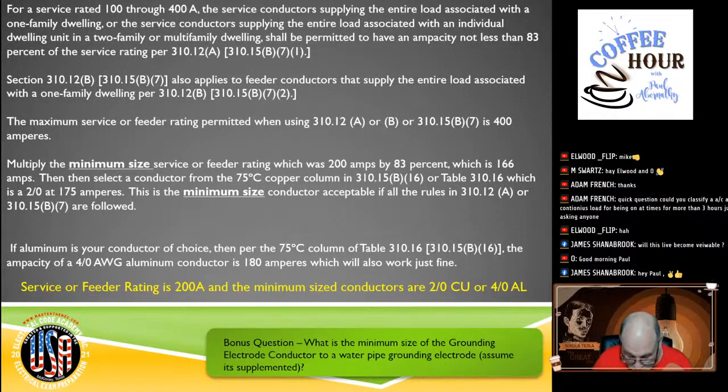Okay. Or you know what? Yep, that's my load. So that's a 200 amp. Couldn't go to 2-aught because that's 175. So we need it based on a 200 amp that's going to be able to handle the 182. So we're good to go. I'm okay with that. If you want to put 3-aught copper in there, I love you. You help out whoever that fictitious person was, okay?